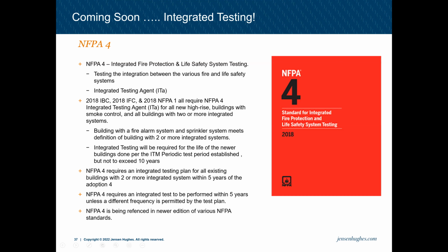Smoke control, as we've talked about, involves a number of systems. So it does have some of the integrated testing feel to it, but it is not specific integrated testing. Integrated testing is somewhat of an owner's rep role, and it tests the integration between the various fire protection and life safety systems. That does require someone who would be an integrated testing agent. Currently, as before, it's not required by code. Cambridge is generally requiring it. Even if it's not required, all the systems should work as intended and as designed.